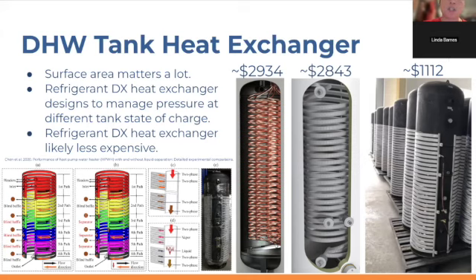So some of the latest innovations in these wraparound tank heat exchangers are what they're calling orifice baffles in the header of the heat exchanger. The header is the main pipe that connects all these branches coming off, and the new headers have holes in them called orifices. When there's hot water up here and only a little bit of cold water at the bottom of the tank, that refrigerant vapor in contact with the hot water will not condense. It will still stay a vapor, and as a vapor, it can go through those holes in the header, bypass all the top refrigerant branches in the heat exchanger, and go straight to where the heat exchange needs to take place.